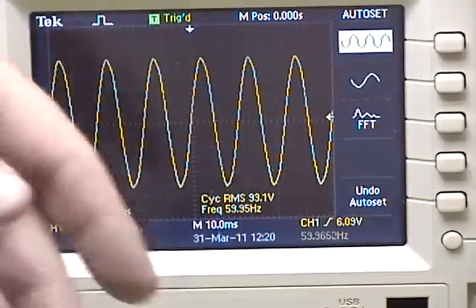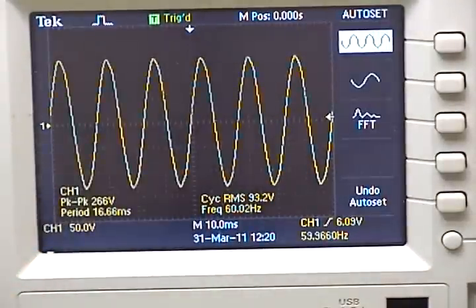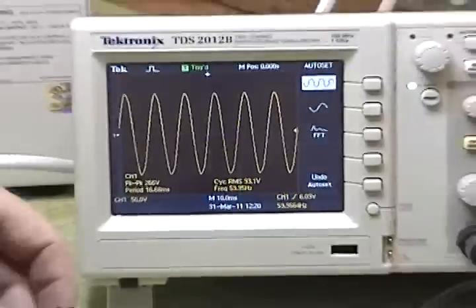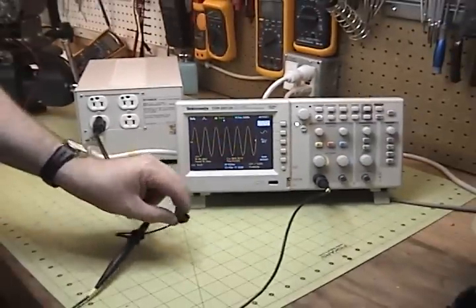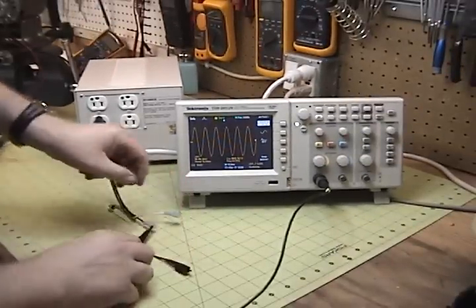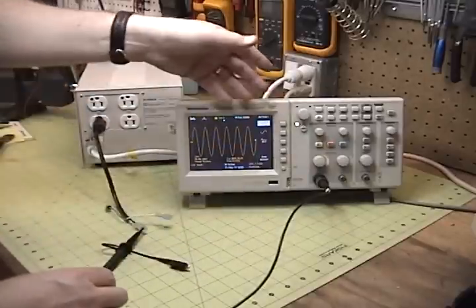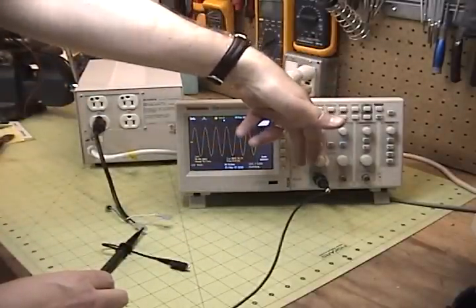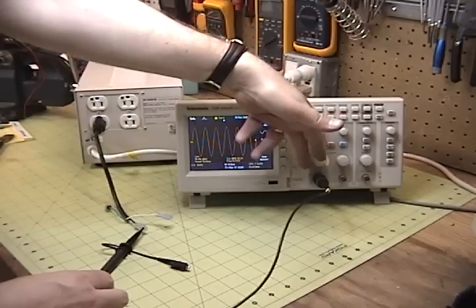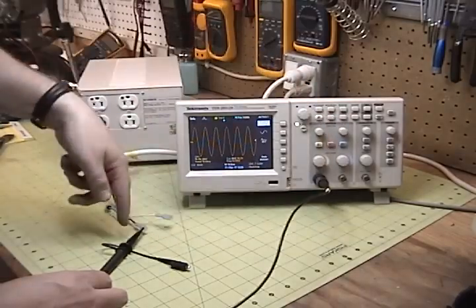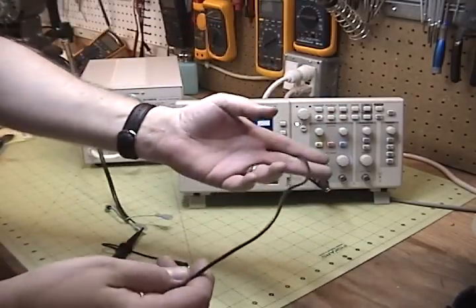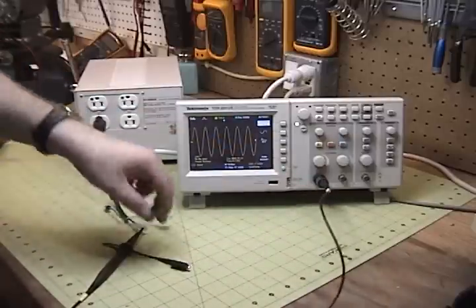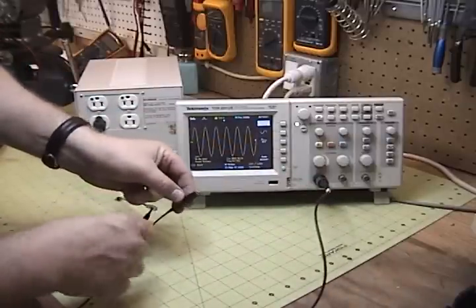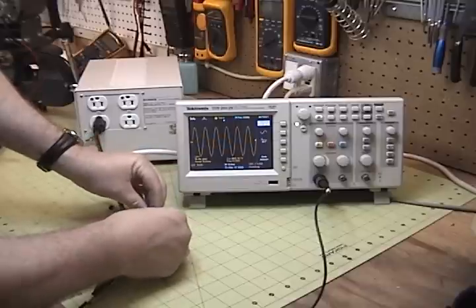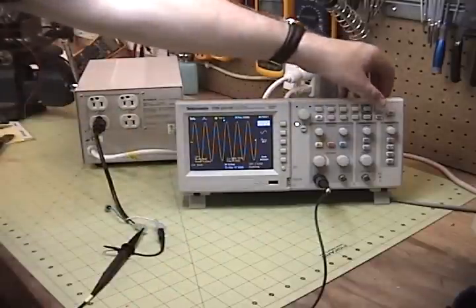That's essentially because I'm not hooking up this ground probe to anything, let me unzoom. I'm just hooking up the high impedance side, so it's actually measuring what it sees over at the chassis. It's measuring between the chassis and the probe tip, with all this in between. But if you hook this directly up to your circuit at the same time, then that all goes away. I'm going to hit auto over here.